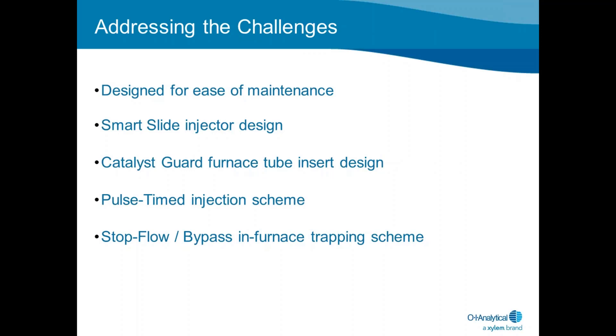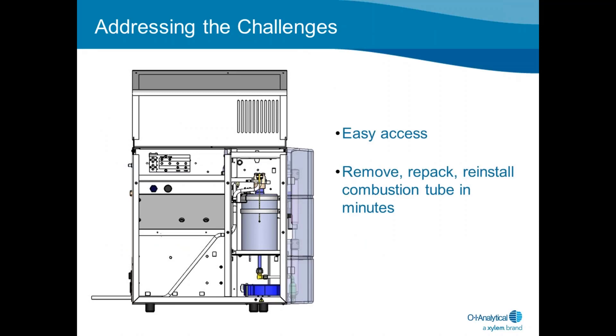For maintenance of the system, the furnace was moved to the front of the system on the side for easy access. You simply lift and take off the side panel, and in most cases the combustion tube can be removed and repacked literally in a matter of minutes instead of hours. Being able to simply get to it in order to work on it was an important design criterion for the instrument.